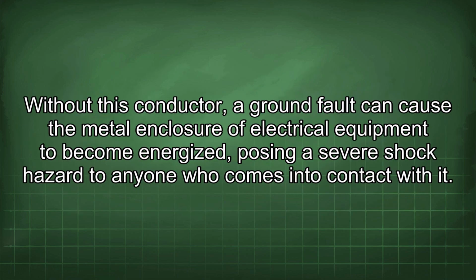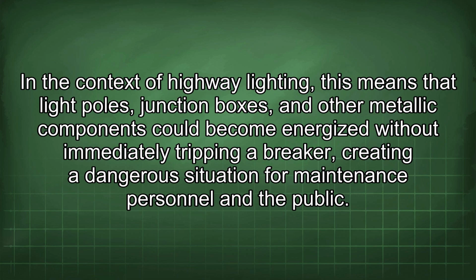Without this conductor, a ground fault can cause the metal enclosure of electrical equipment to become energized, posing a severe shock hazard to anyone who comes into contact with it. In the context of highway lighting, this means that light poles, junction boxes, and other metallic components could become energized without immediately tripping a breaker, creating a dangerous situation for maintenance personnel and the public.